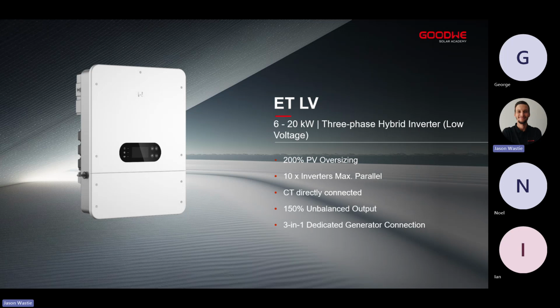All right, so let's get started. So this is the ETLV. Like I mentioned earlier, the ET stands for energy storage three-phase, and then low voltage for the battery connections. We've got a wide variety of this inverter type, from a 6 kilowatt all the way up to 20. In the region that we currently are in, we focus more on the three bigger units, which is a 12 kilowatt, a 15 kilowatt, and a 20 kilowatt unit.